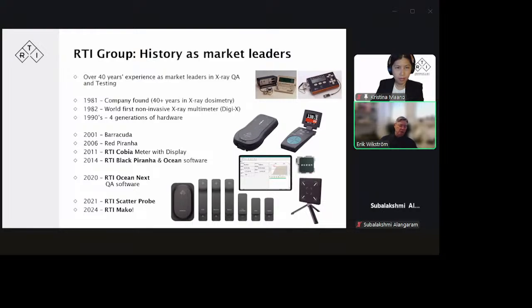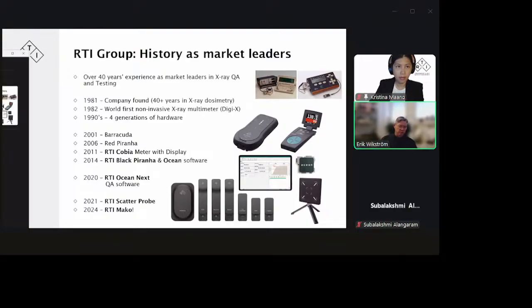And before that, of course, to measure a kV, for instance, in an X-ray machine, you had to disconnect the high tension cables and fit them into a voltage divider, and then make a measurement, connect your oscilloscope or a voltmeter, and then put everything back. So that would take, in the best case, like 30 to 45 minutes for one exposure. Being able then just to put the detector into the field, make one exposure, and have all those data in 2 minutes was a vast improvement, of course.